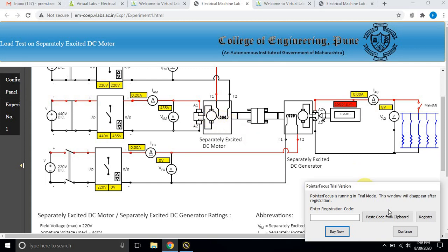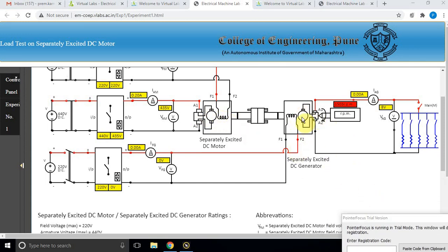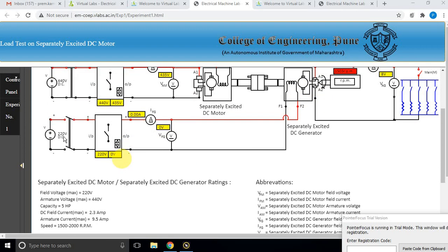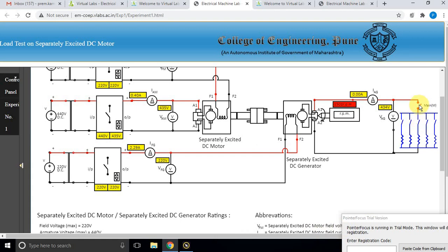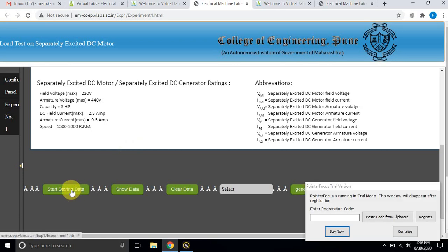After reaching rated speed, apply load. To apply load, first you need to excite the DC generator. Close this switch and adjust the field excitation to 220 volts, 2.29 amps. Then close the load switch — the main switch — and store the data.